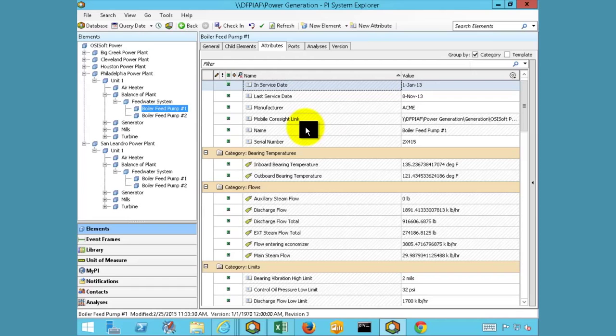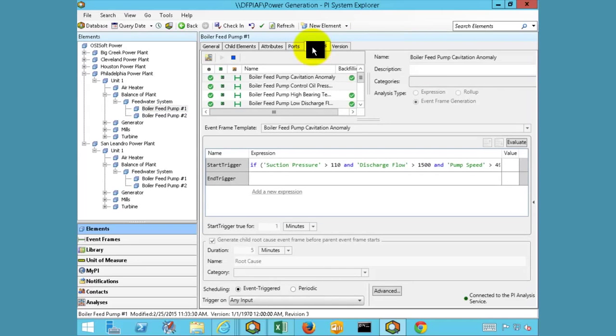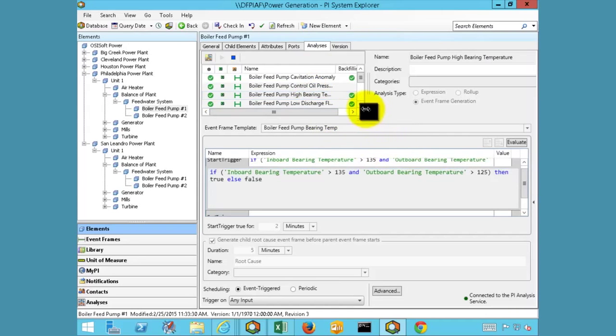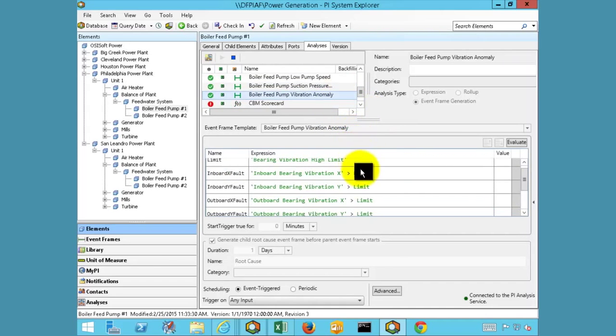The data can also be used in analysis that can turn the raw data into something more actionable. In our case, we wish to flag critical events and make them available through the Event Frame database. After selecting the analysis tab, we can see all of the different types of analyses being used to flag critical events in our system. The logic, in the case of the bearing temperature, is a simple comparison — we are flagging an event when the inboard and outboard bearing temperatures violate predefined limits. In the case of the vibration data, we are doing something similar, but instead of hard-coding our limits into the analysis, we are referencing data that may come from an external table. If these limits are changed in the table, then the analysis will use the updated limits to flag the critical events.